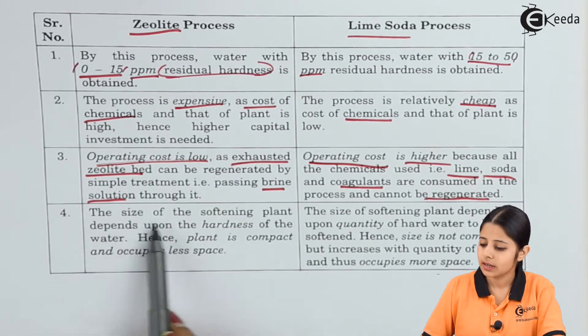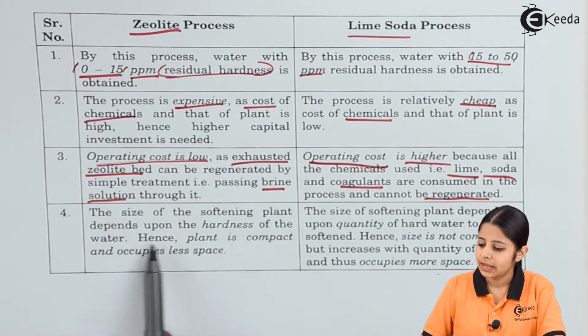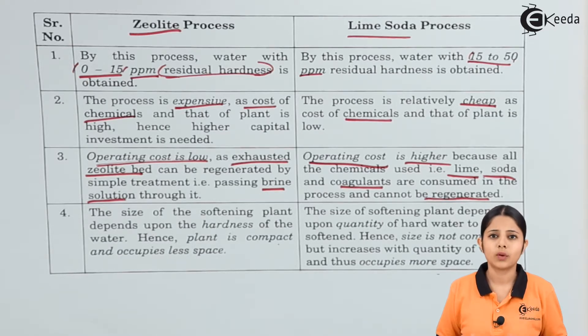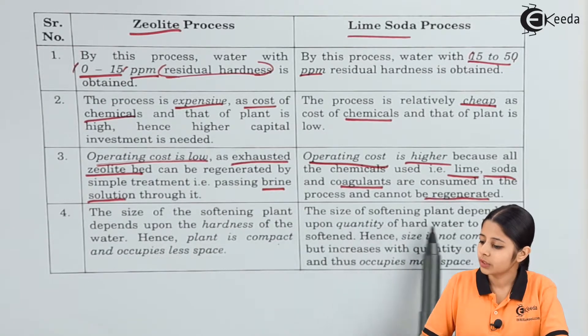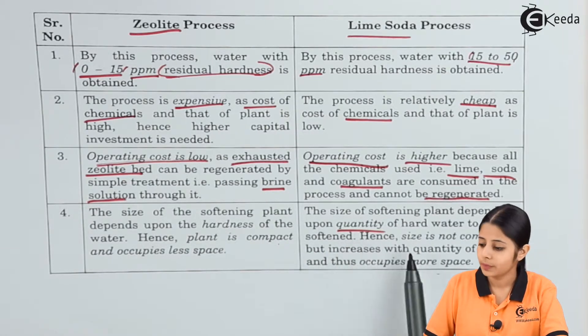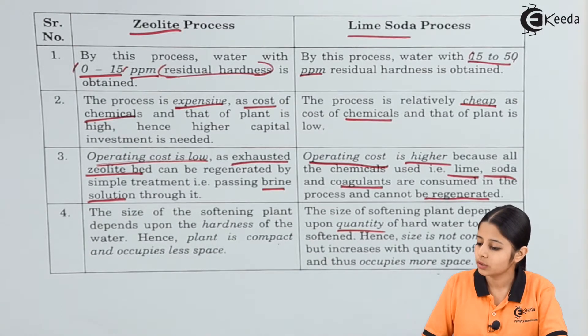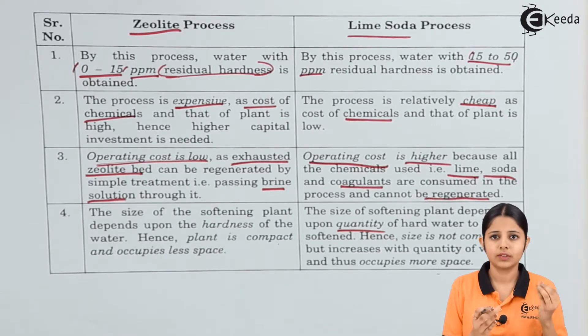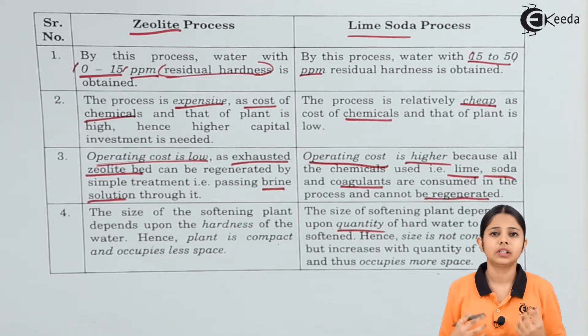Point four: for the zeolite process, the size of the softening plant depends on the hardness of the water, so the plant is compact and occupies less space. You only need a zeolite bed — water is poured in, it reacts spontaneously, and soft water is obtained. For the lime soda process, the plant size depends on the quantity of water to be softened, so it is not compact and occupies more space as quantity increases.